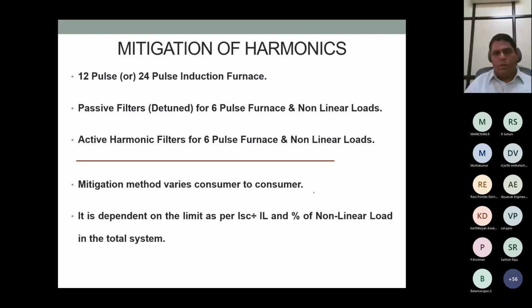So it depends upon how it should be done. It cannot be generally told, sir, change your furnace, things will happen, it is okay, or put a detuned filter, it will be okay, or put an active harmonic filter. So it is not a generalized way, we cannot say. It will be consumer dependent, and depends on how much a particular consumer is exceeding his limit. Say, for example, his limit is 12% and his TDD value is about 20%. That means a particular type of filter mitigation mechanism has to be followed, and he has to bring it down.